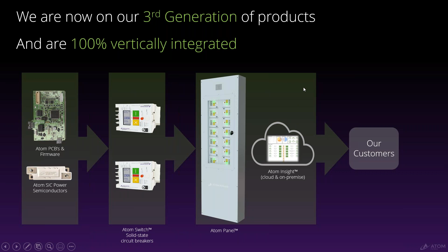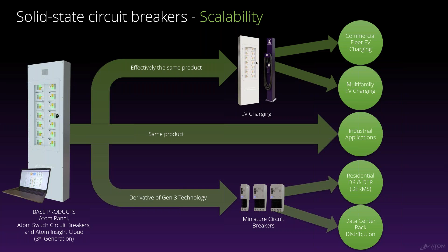This includes EV charging, which is great for commercial, fleet, and multifamily—more large scale, 3-phase applications where you'd see something like 208 volts. That's great for our panel here. Then, using that same technology, we've now shrunk it down, and we're coming out next year with a miniature circuit breaker that will fit in a residential or commercial load center, which can be used for demand response, distributed energy resources, and even in data centers.